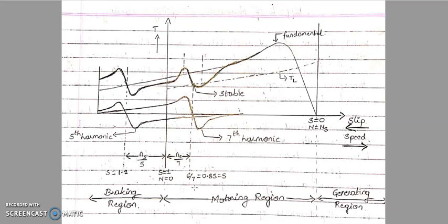Motor draws high current in order to supply the torque and all. So due to absorbing or taking more current, what happens is the power factor drops, and your motor will get heated up. Again, if this proceeds, surely the motor performance will be severely affected. The power factor will also be very low here. Hope you understood this.